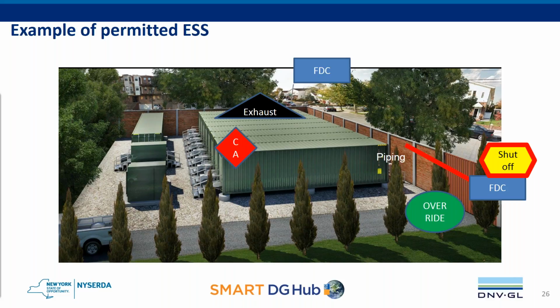They felt that the clean agent wasn't capable of absorbing the heat from a battery fire, so they had the companies put in a piping system, which is right here. That piping system would be a straight pipe that would go into each one of these containers, and they would have a closed head sprinkler system in there that would burn out at 212 degrees. The FDC here stands for the Fire Department Connection. As you can see, I have 2 in the picture, 1 at each side, where the fire department could hook up their engine right to the Fire Department Connection and then start to put water in there in the event of a catastrophic failure.